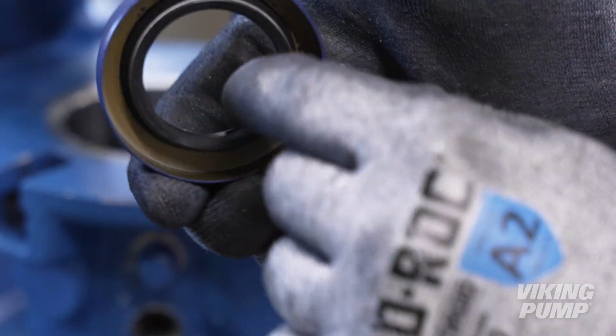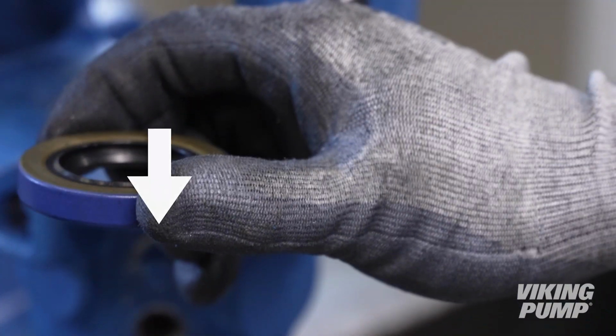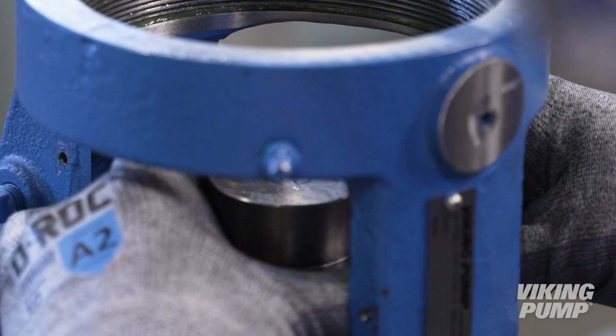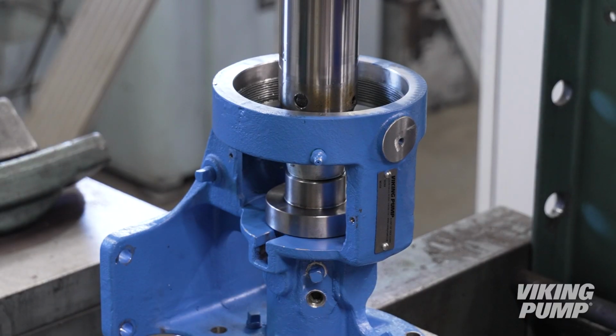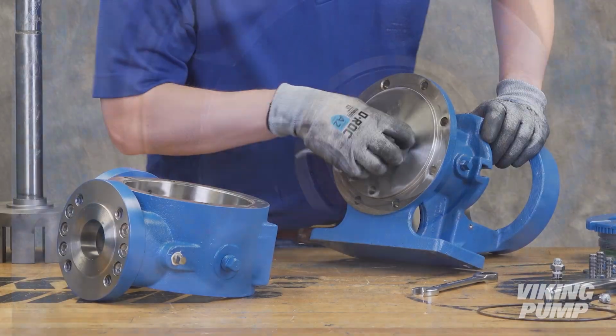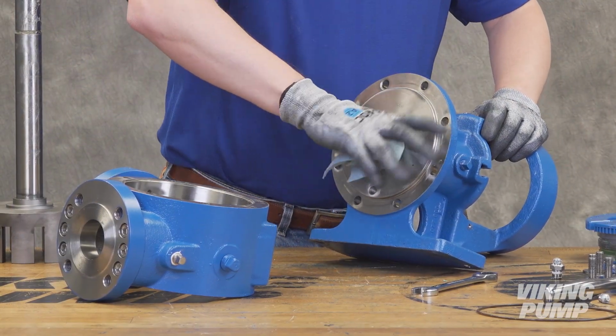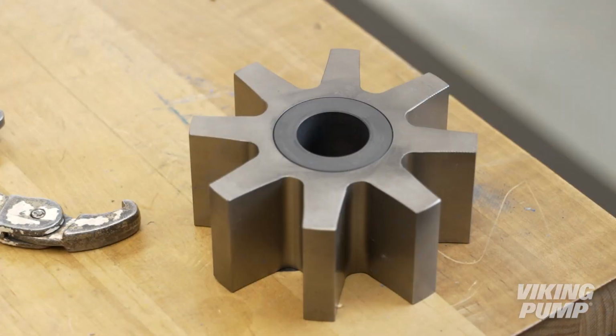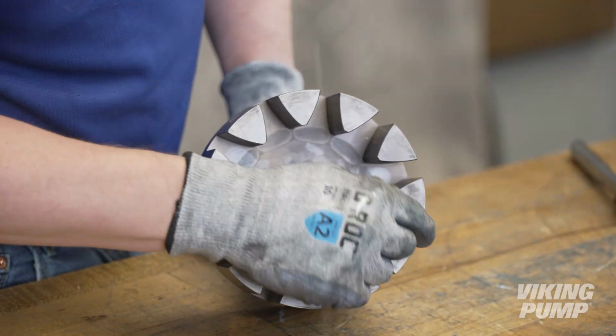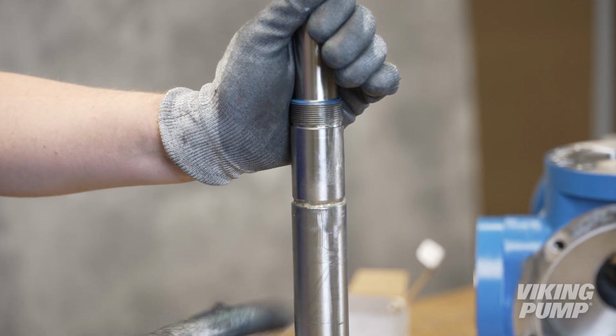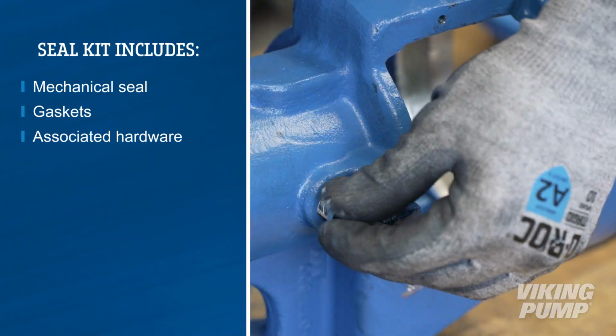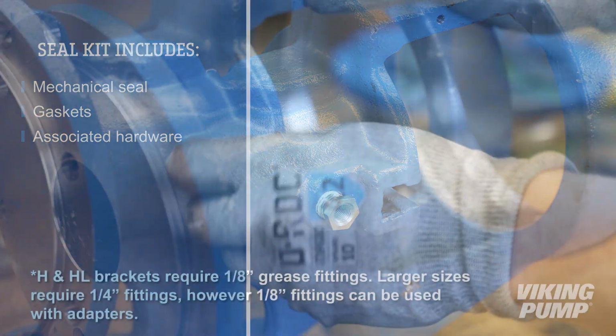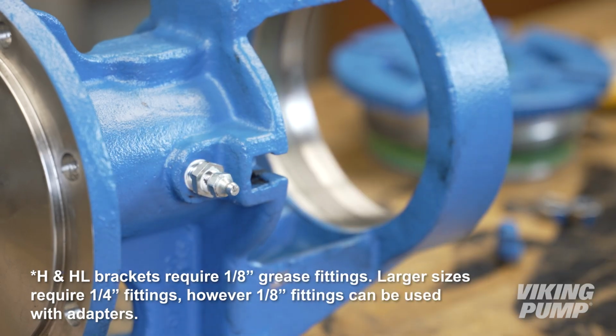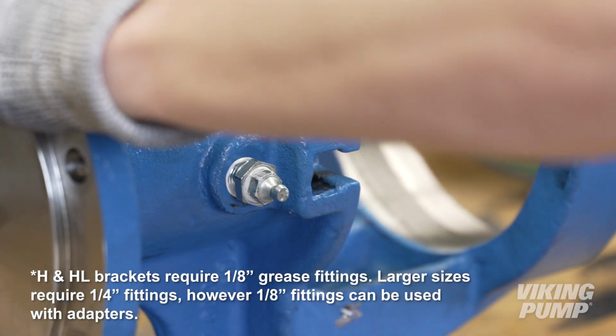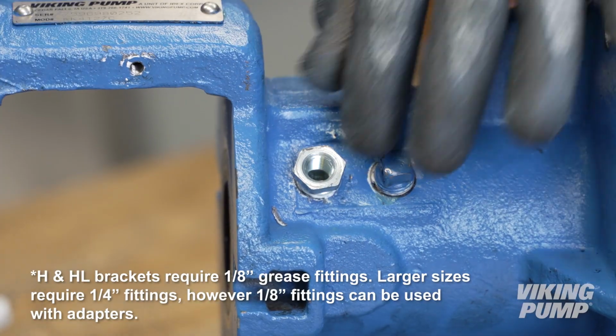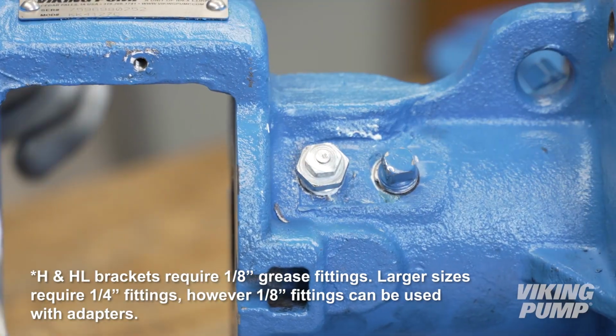Lubricate and place the bracket lip seal with the spring side down toward the casing end of the pump. Using a flat press fixture, fully press in the lip seal. Before reassembly, ensure the casing, bracket, head, idler pin, idler, and rotor shaft are free of any debris or wear. Replace any worn components. Using thread sealant, install a grease zerk on one side of the bracket. Use an adapter fitting if needed. On the opposite side, install a grease relief fitting. Use an adapter fitting if needed.